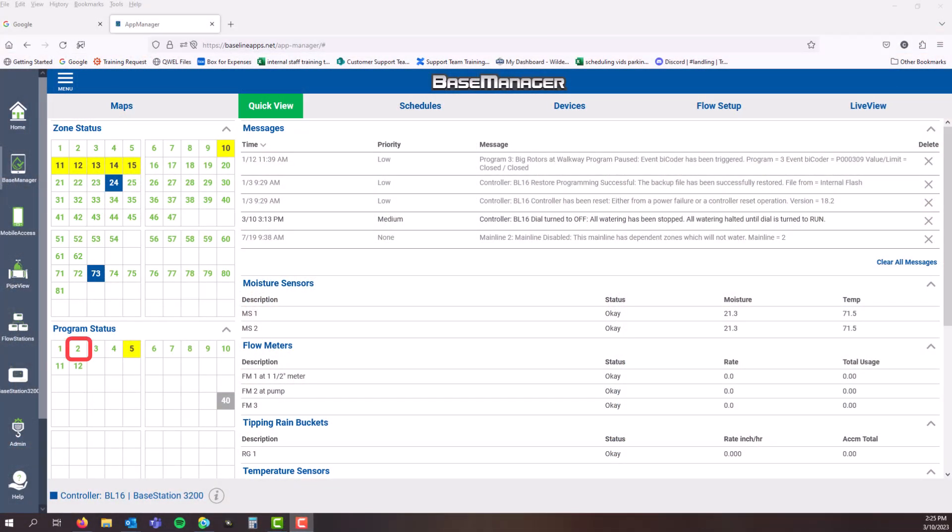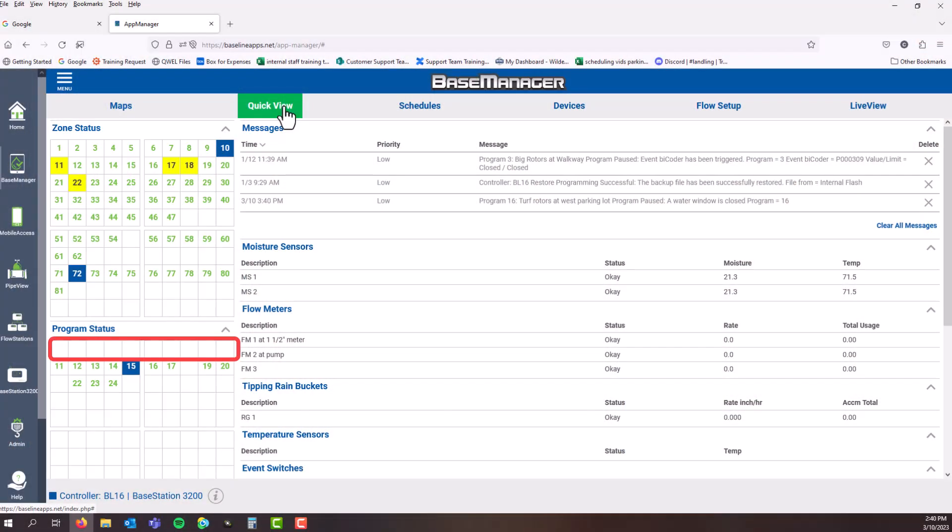Let's focus on ordering. If I've got 20 programs I decided to use, should I start at program one, two, three, four? No, let's not do that. I start people at program 10 or higher. There's a natural order of priorities — if I leave one through nine open for when I need special programs to run at certain times without having to give them a priority, I can do it. I've already got 99, so there's lots of room. This is a good practice — leaving a gap there. Why would people leave a gap?